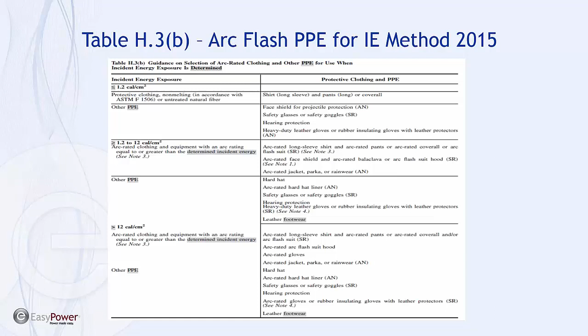So whatever we determine to be the worst case incident energy, we can actually suit up and layer up. And in the case of 1.2 to 12, we may be able to do it with a single layer. As we get to the higher levels, greater than 12 calories, then it may take multiple layers to get there, but we can still suit up just to that determined incident energy level. So you can see this ends up being much more, I don't want to say flexible, much more deterministic in terms of we know the danger, we've calculated the worst case danger, now we protect our people to that point, and they have the most optimum working condition in terms of both being safe and not overburdening them with extra equipment that they don't necessarily need.